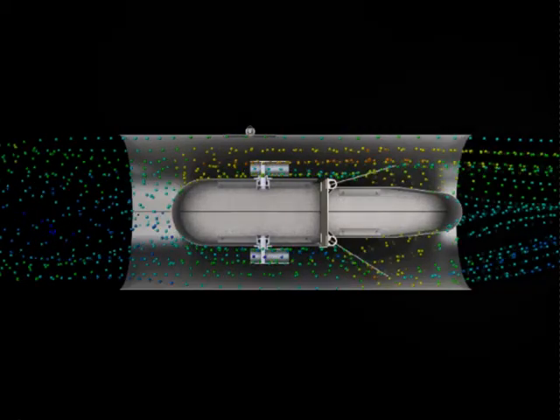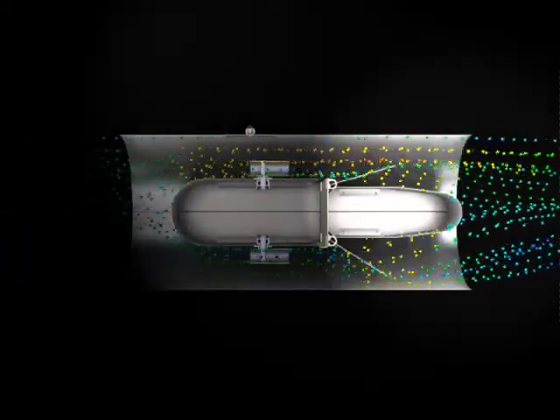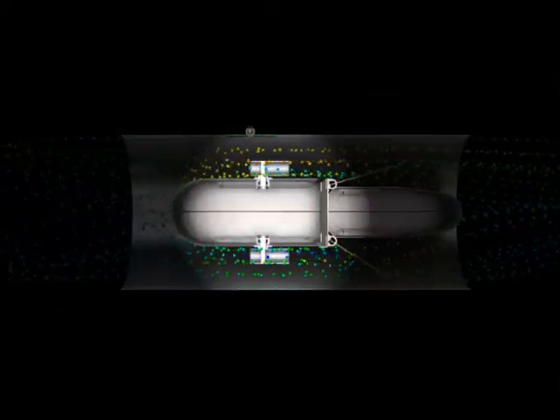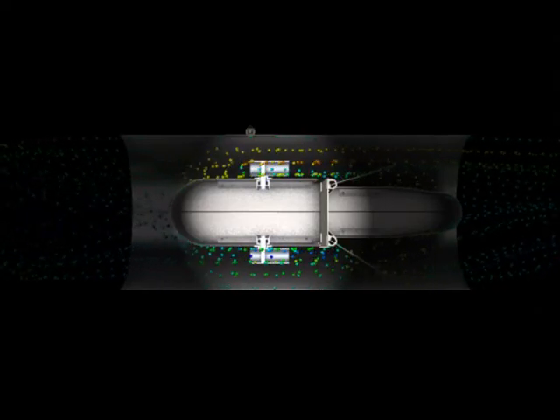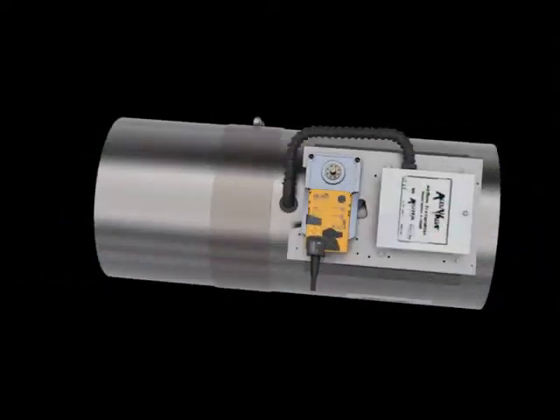The static regain section ensures the minimum possible pressure drop for maximum energy savings. Within the compression chambers are the Vortex Shedding Airflow Sensors, which provide a high degree of accuracy throughout the entire flow range for true airflow feedback.